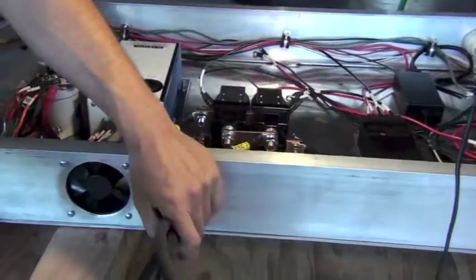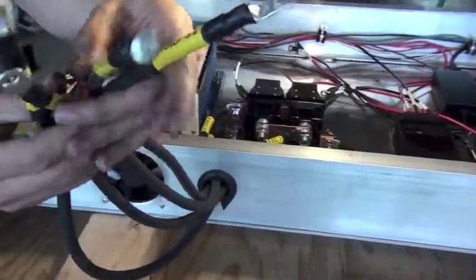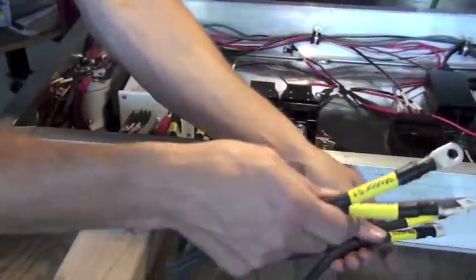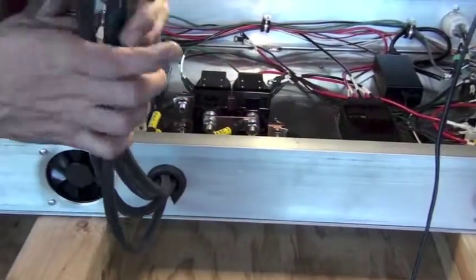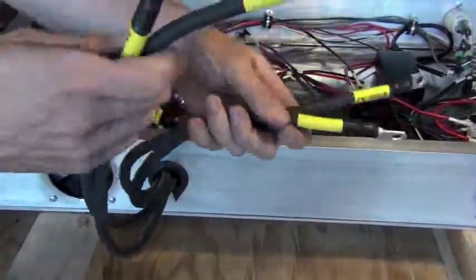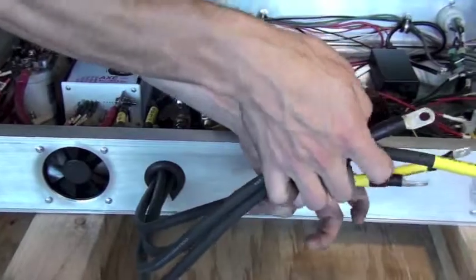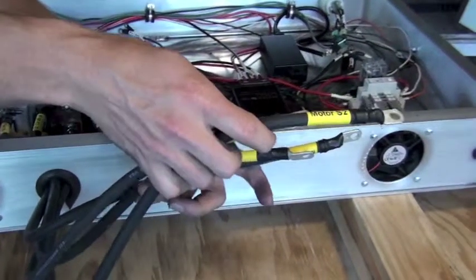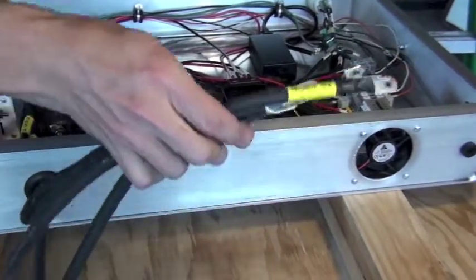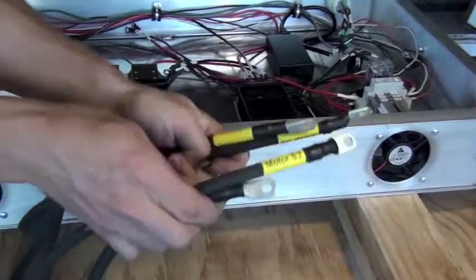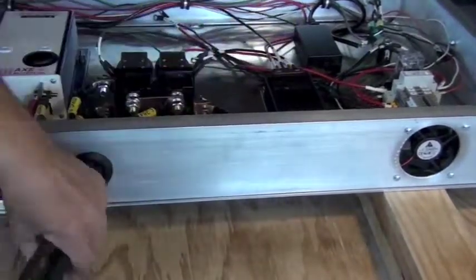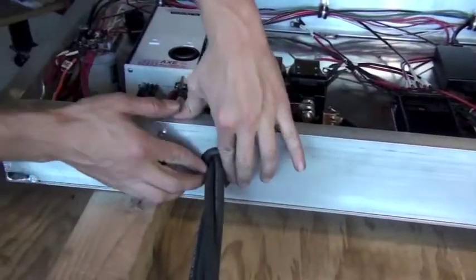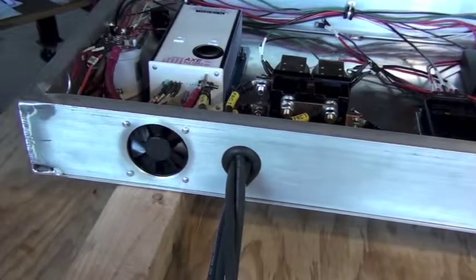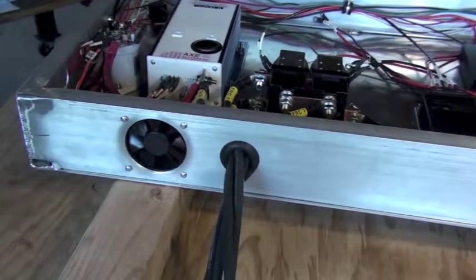We now have our 4 motor cables ready to be attached to the motor when the high voltage control enclosure and the motor are mounted into the vehicle. And the cables will have a small amount of play in them in the event that they have movement during the suspension travel while we operate the vehicle. They're efficiently entering and exiting the box through the sealed opening.